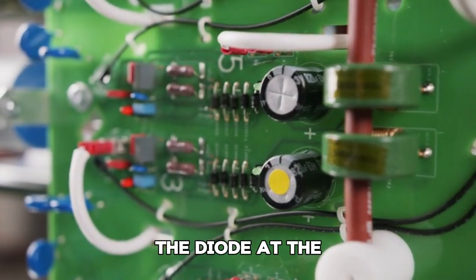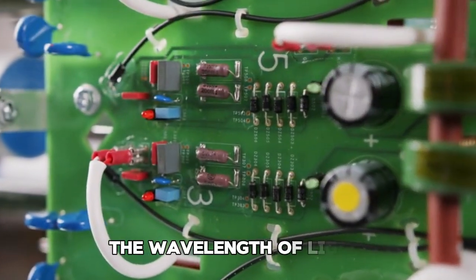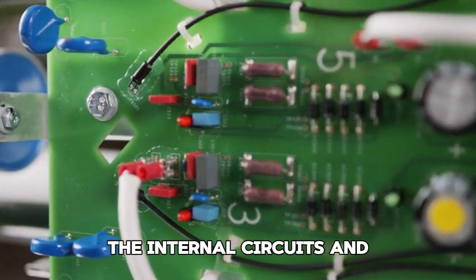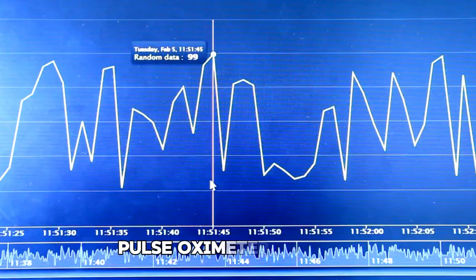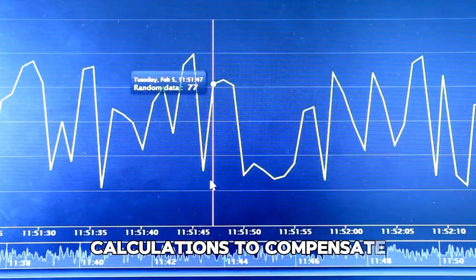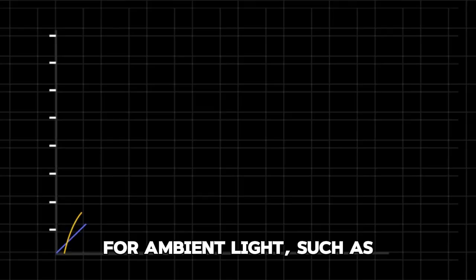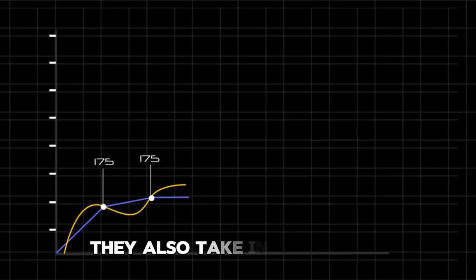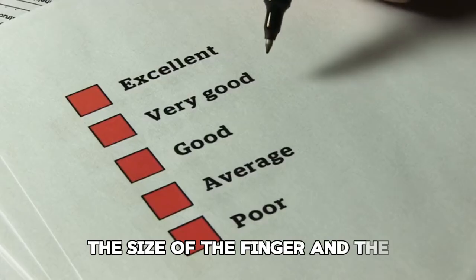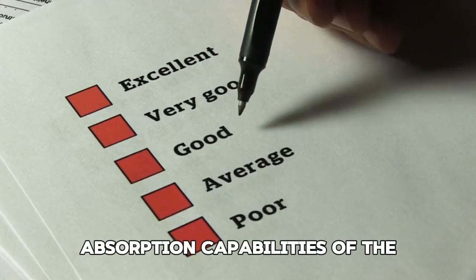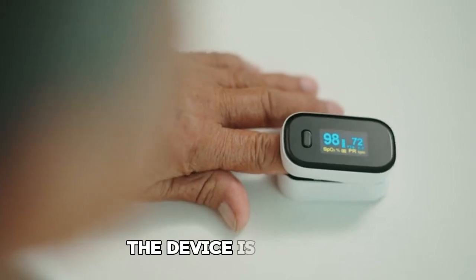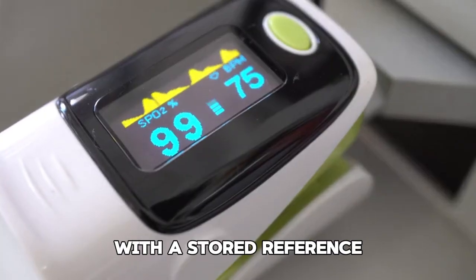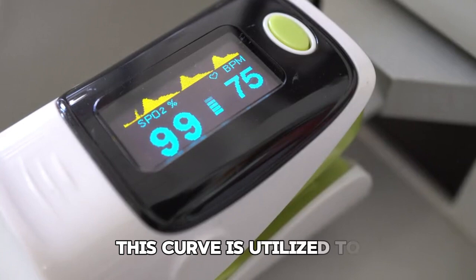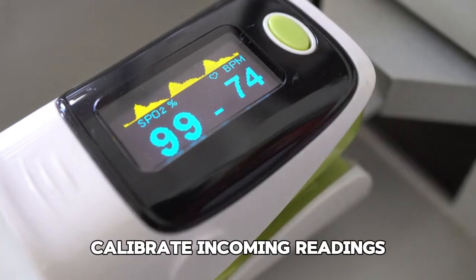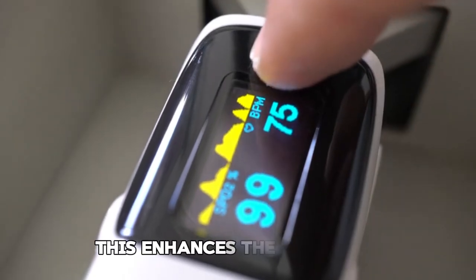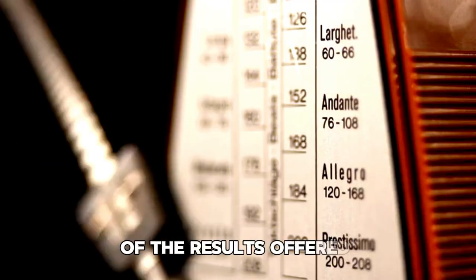The diode at the receiving end can detect the wavelength of light. The internal circuits and processing components of the pulse oximeter perform calculations to compensate for ambient light, such as room light or sunlight. They also take into account the size of the finger and the absorption capabilities of the surrounding tissues. The device is equipped with a stored reference curve in its memory. This curve is utilized to calibrate incoming readings and standardize them. This enhances the accuracy of the results offered.